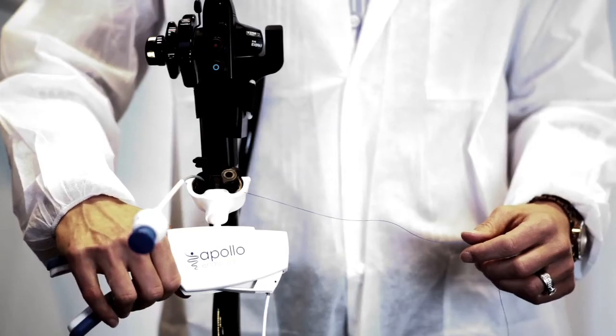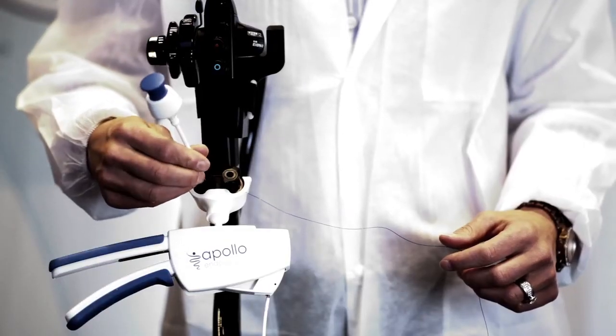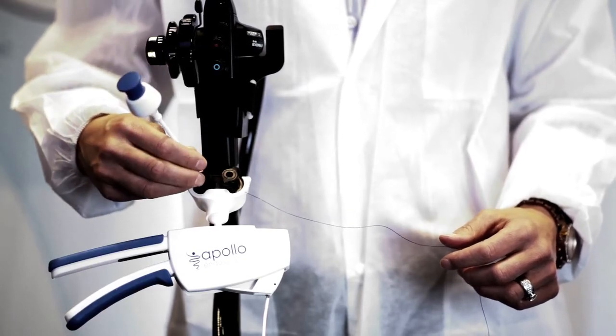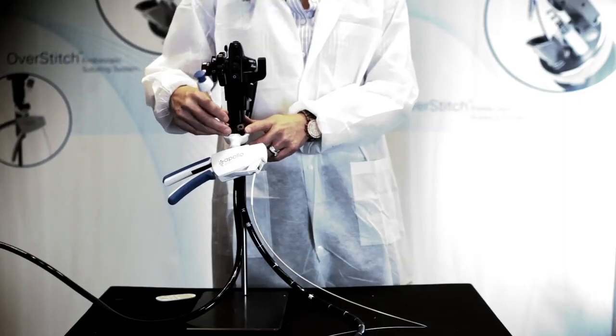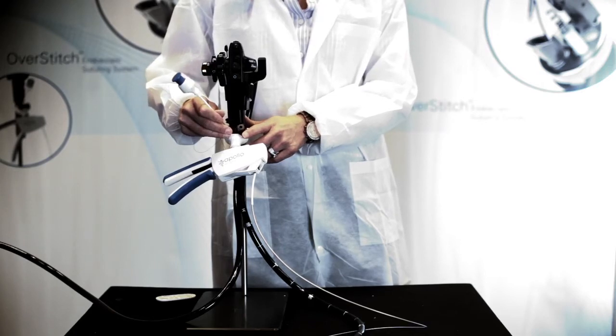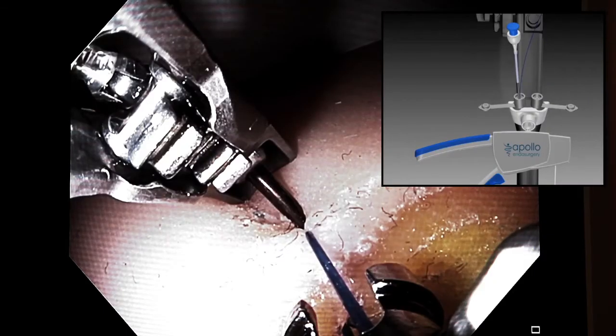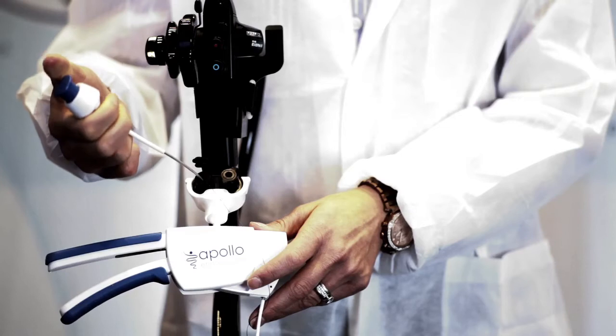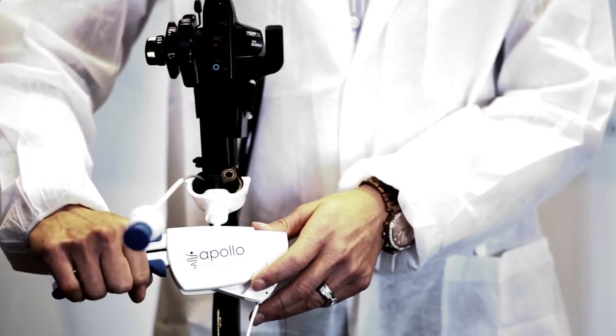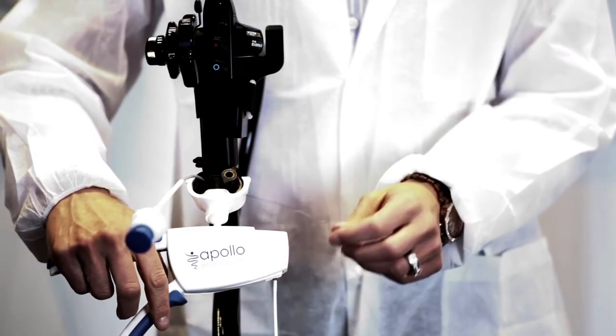To place a stitch, the device is positioned such that the curved needle arm and anchor pass through the tissue. The handle is then closed to advance the anchor through the tissue. After this, the anchor is retrieved with the anchor exchange catheter. Advance the catheter down the therapeutic channel until resistance is met. Next, brace your fingers on the biopsy valves and pull back on the anchor exchange catheter until a pop is felt. Immediately stop pulling on the catheter and squeeze the handle open to complete the stitch.